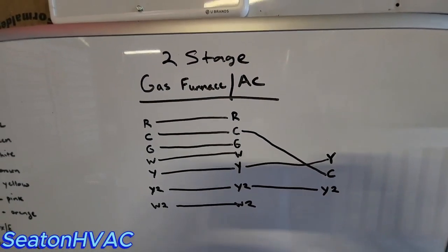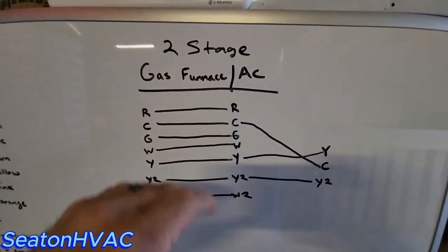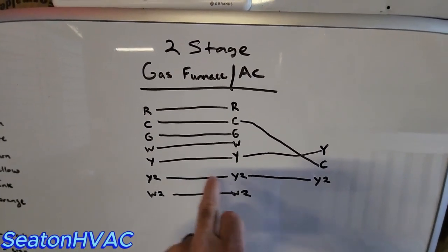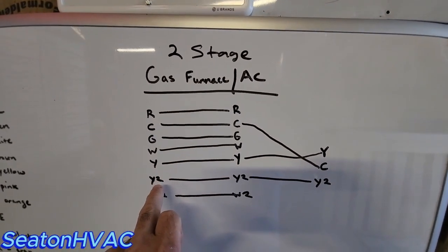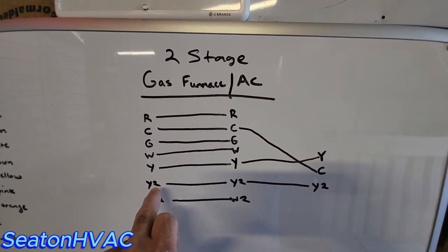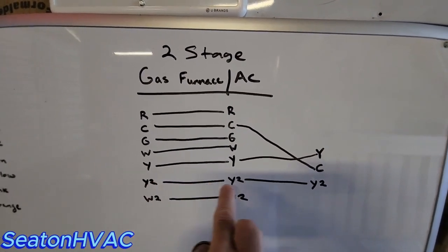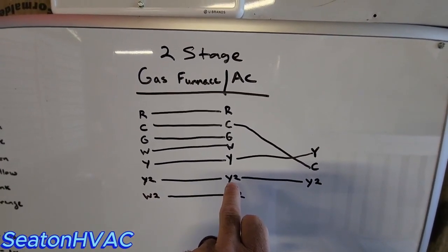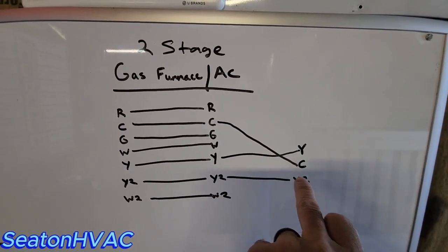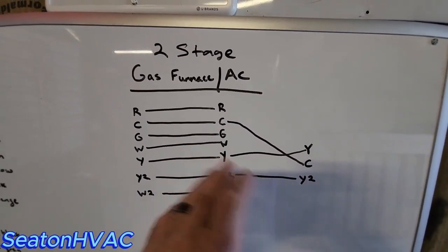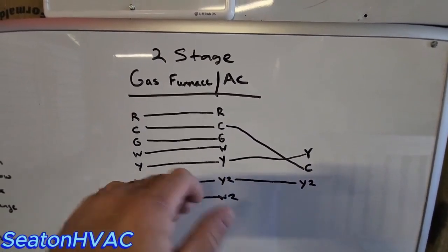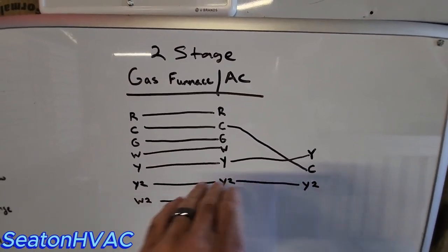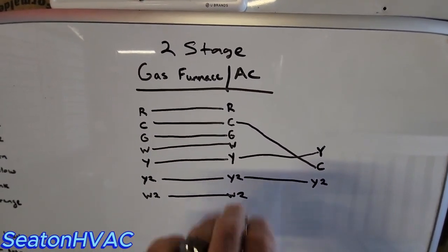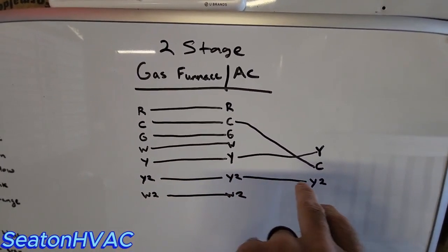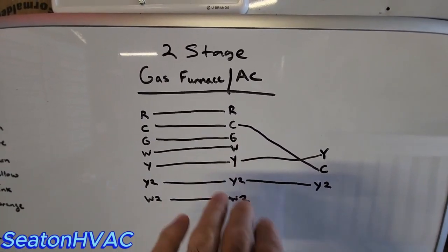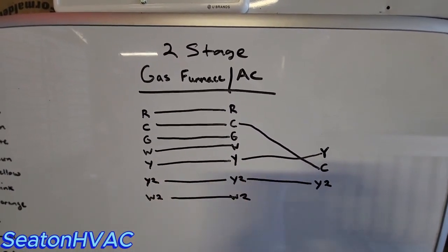Okay, guys, two-stage gas furnace AC. Same as the single stage, but now what you're adding in is your Y2. Second stage compressor going outside. So you're going to have that terminal on your thermostat and on your gas furnace and out to your air conditioner. And I use pink for that. Just what I use. Some guys use brown, but I like to do it the same every time. So Y2 for pink. Even some of the manufacturers have that as the color inside of their equipment. So easy to mess it up if you don't do the same thing every time.